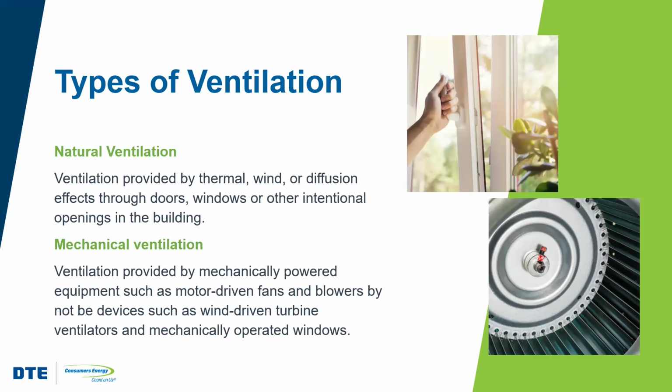So ventilation comes in two primary forms. We've got natural ventilation, which relies on wind and stack effect, or the chimney effect, to cool a home without using the HVAC equipment. Wind can naturally ventilate the home. It enters through open windows, through open doors, depending on the wind's orientation, obviously. When that wind blows across the house or against the house, wind comes in one side and goes out the other.